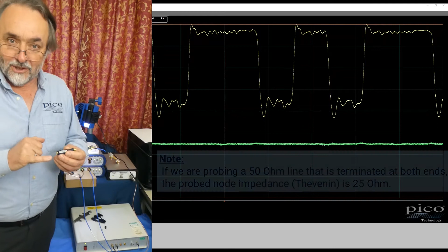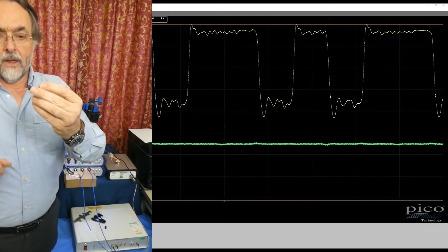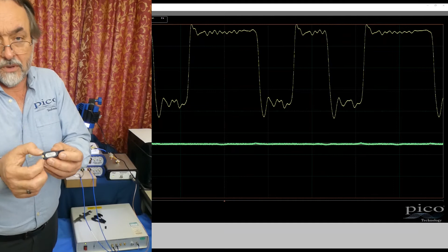So a next best option is that if we put 2 grounds either side like that, we can make a coplanar transmission line with the 2 grounds either side of the tip. The impedance of the line is created by, one, the diameter of the probe tips here, and also their spacing, and that's why the spacing is relatively wide. We want to try and make a transmission line of a relatively high impedance, and with this spacing of these tips we're achieving something like 200 to 250 ohms as a transmission line into the probe.